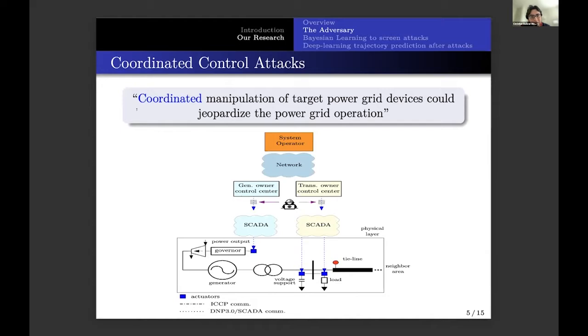And in particular, we are interested in stopping coordinated control attacks. The attack against the Ukrainian power grid was a coordinated control attack. By coordinated, we mean the manipulation of multiple power grid devices in order to jeopardize the power grid operation. In the figure that you're seeing there, for example, we are assuming the adversary has reached the SCADA system of generator owners and transmission owner operators, and they are ready to either operate the generators, they're going to disrupt the power output of the generators, or they're going to open a transmission line, like what happened in Ukraine.